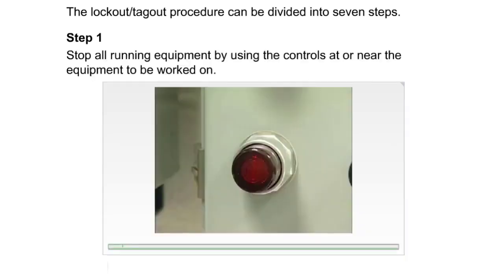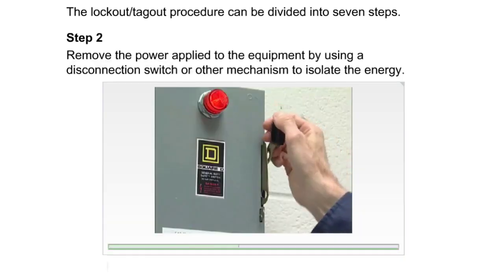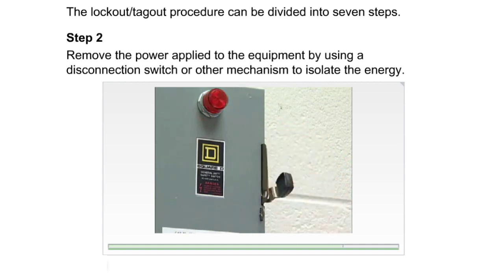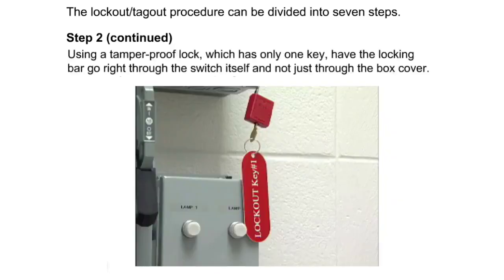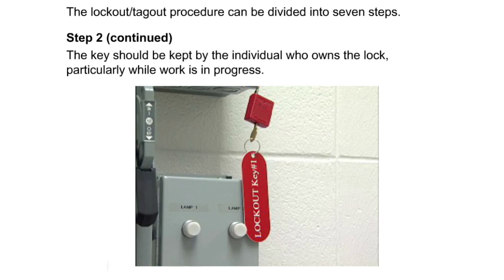Step 1. Stop all running equipment by using the controls at or near the equipment to be worked on. Step 2. Remove the power applied to the equipment by using a disconnection switch or other mechanism to isolate the energy. Using a tamper-proof lock, which has only one key, have the locking bar go right through the switch itself and not just through the box cover. The key should be kept by the individual who owns the lock, particularly while work is in progress.